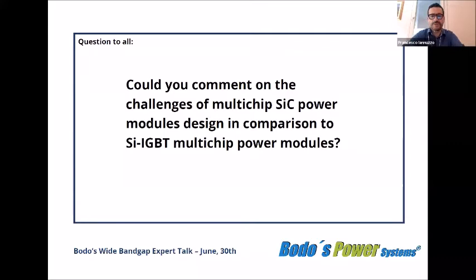I can make a short comment. Thank you, Francesco. Yes, I can tell you what I see from a reliability perspective. Silicon carbide is a great material, and power density can be raised by a factor of 2, 3, even higher than that. And this makes chips smaller than the IGBT silicon counterparts. But one of the issues I tried to point out recently is that this dramatically reduces the area you have for landing your bond wires. And this shifts the problem from the semiconductor itself to the package. So you are incredibly increasing the current density of your bond wires.